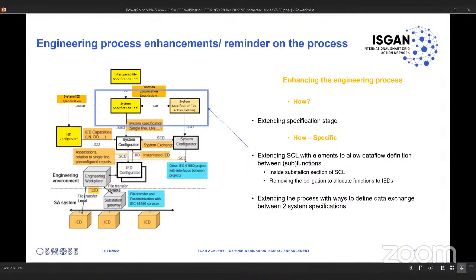The first enhancement is about extending the specification stage. We extended SCL with elements to allow data flow between functions and sub-functions, done inside the substation section of SCL. One of the main improvements is that it's no longer mandatory to allocate your functions to IEDs in order to specify data flow — as a user, you can now create a vendor and IED-allocation-independent system specification. Another improvement is the exchange of specification between two different projects, useful for example when two substations need to exchange teleprotection trips.